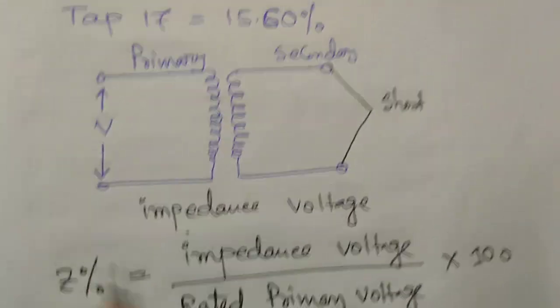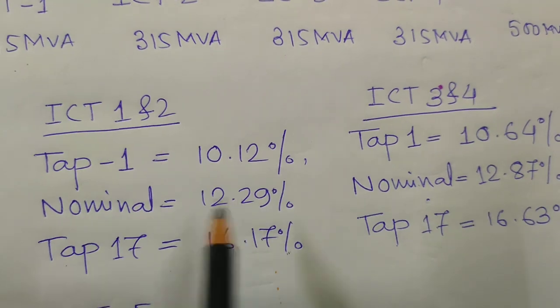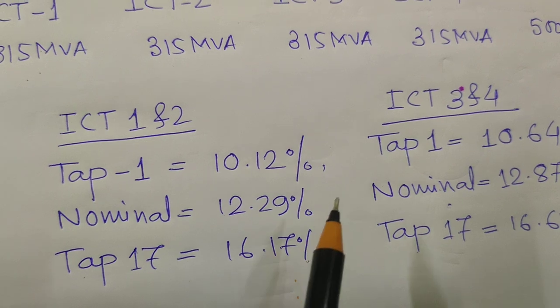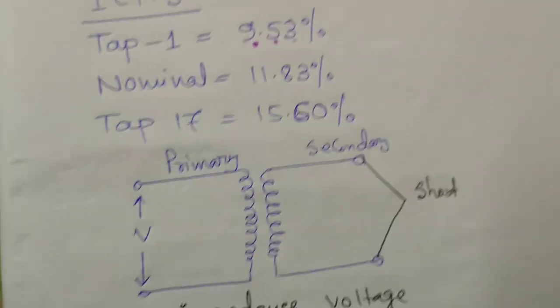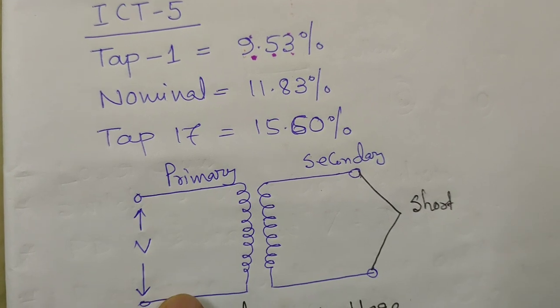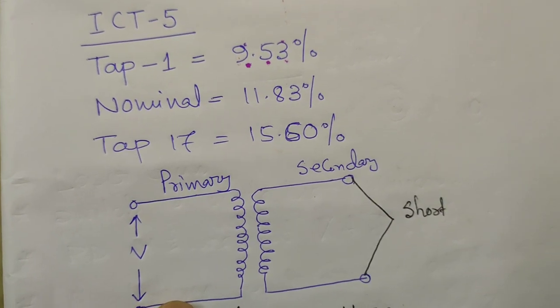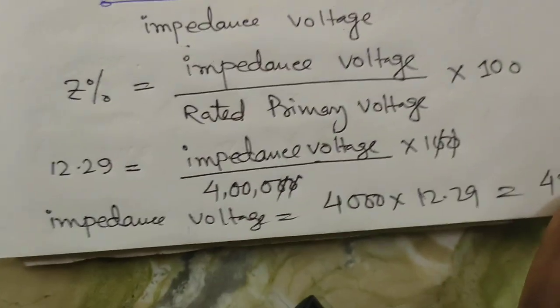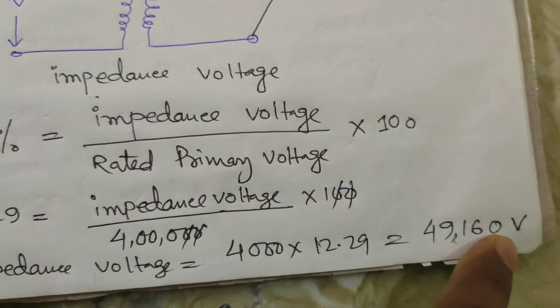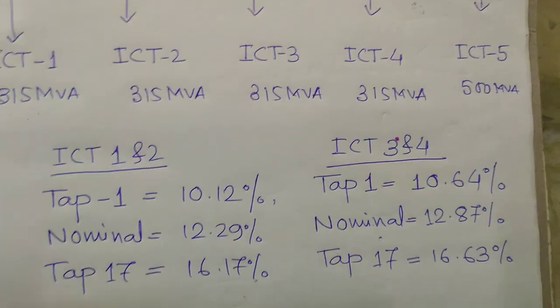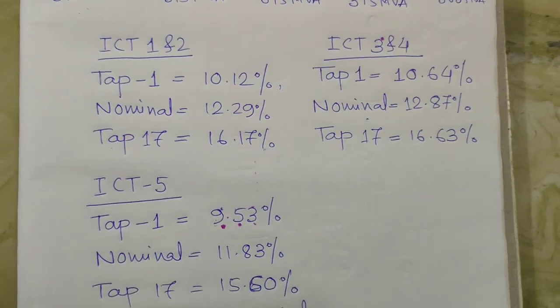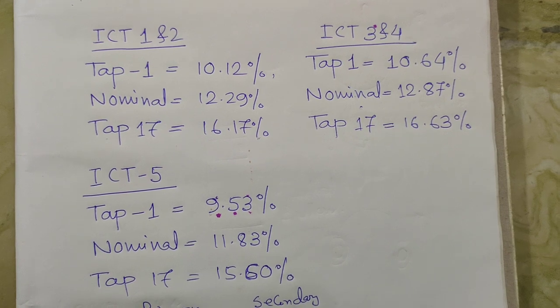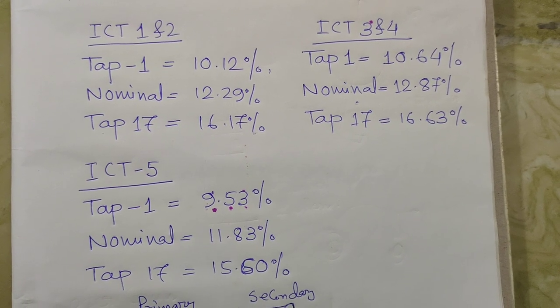So the impedance voltage of this ICT at the nominal tap is 49.16 kV. This means the minimum voltage you have to apply to the transformer to get the rated short circuit current is 49.16 kV. This is a very interesting and important topic regarding the percentage impedance of transformers. Thank you for watching.